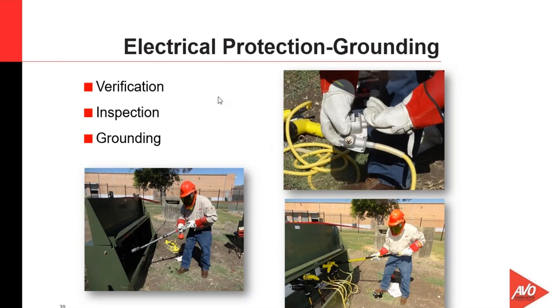These pictures depict the proper procedure or the process for installing grounds. Number one, we have to verify absence of voltage. So we have to test the system that we're going to install PPE grounds on with an approved test device. We pre-test and post-test the tester to make sure it actually works, and we verify absence of potential prior to installing grounds. Inspection of the grounds prior to use is also required, so we would do a visual inspection to ensure that all the fittings are tight, the connections are there, there are no cuts or damage to the cable itself.